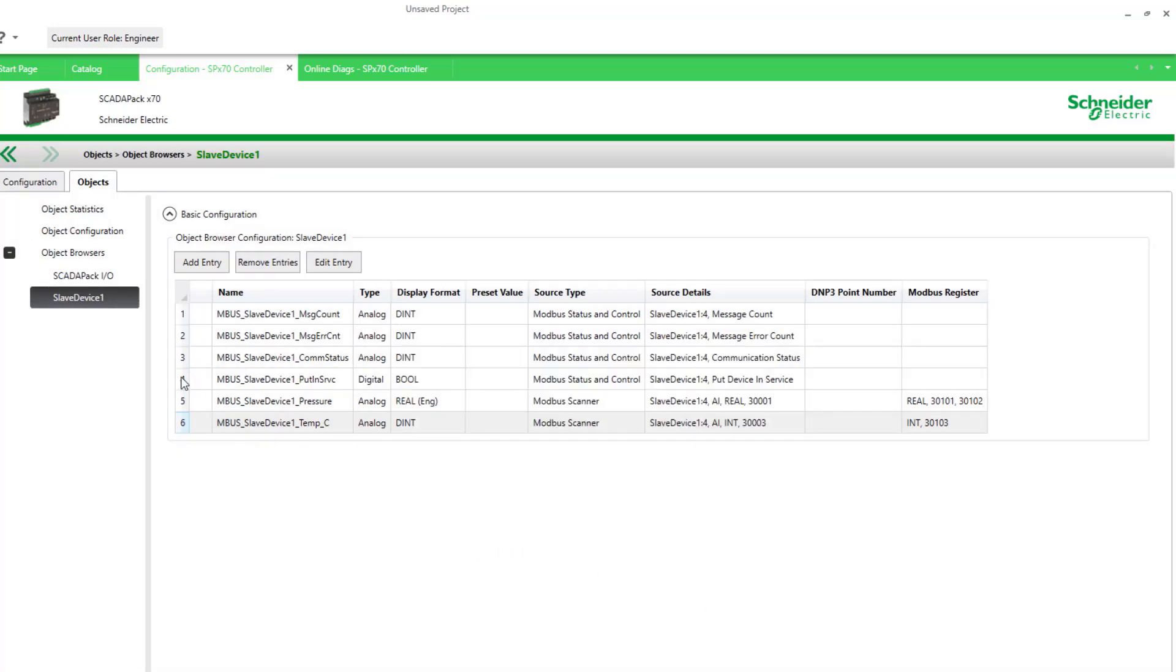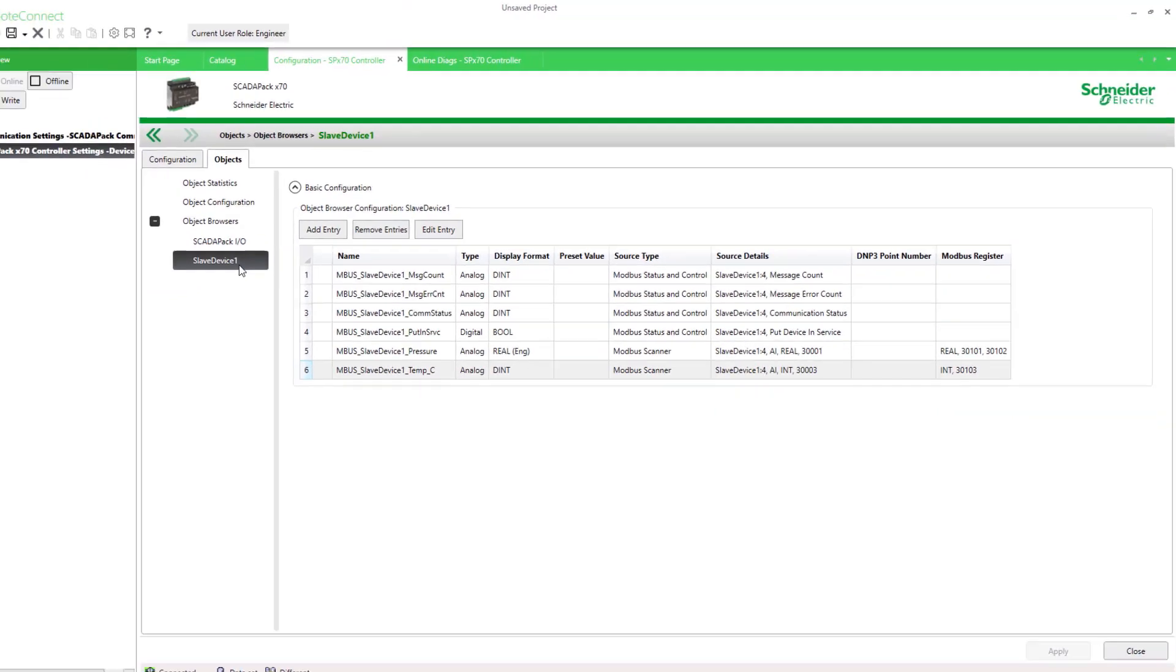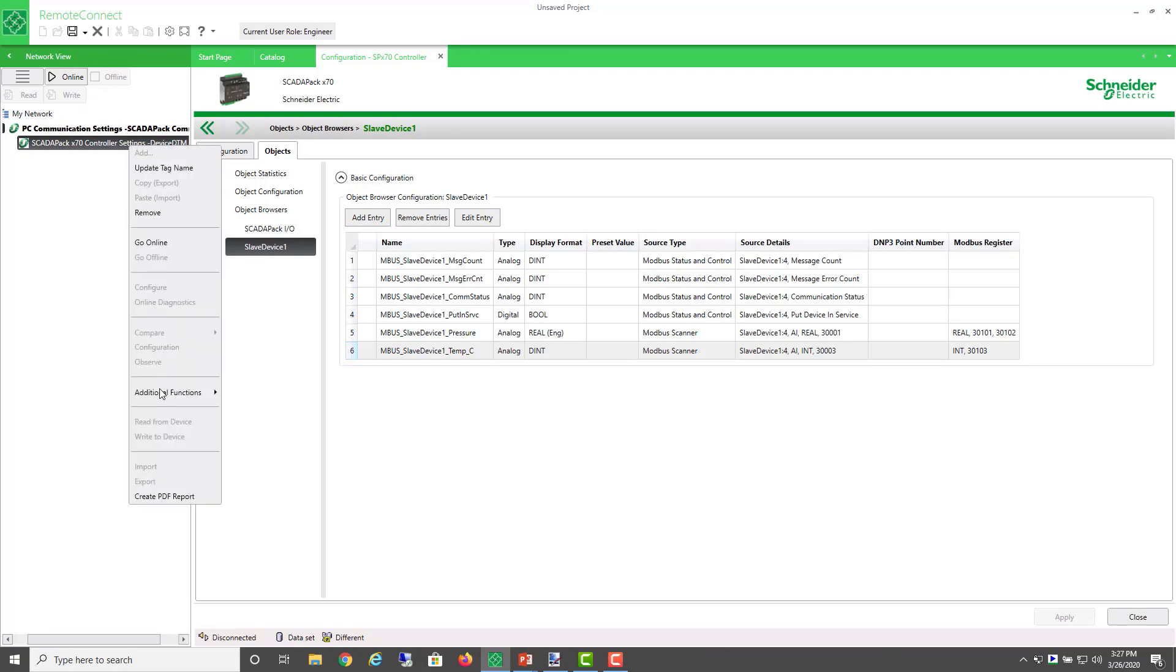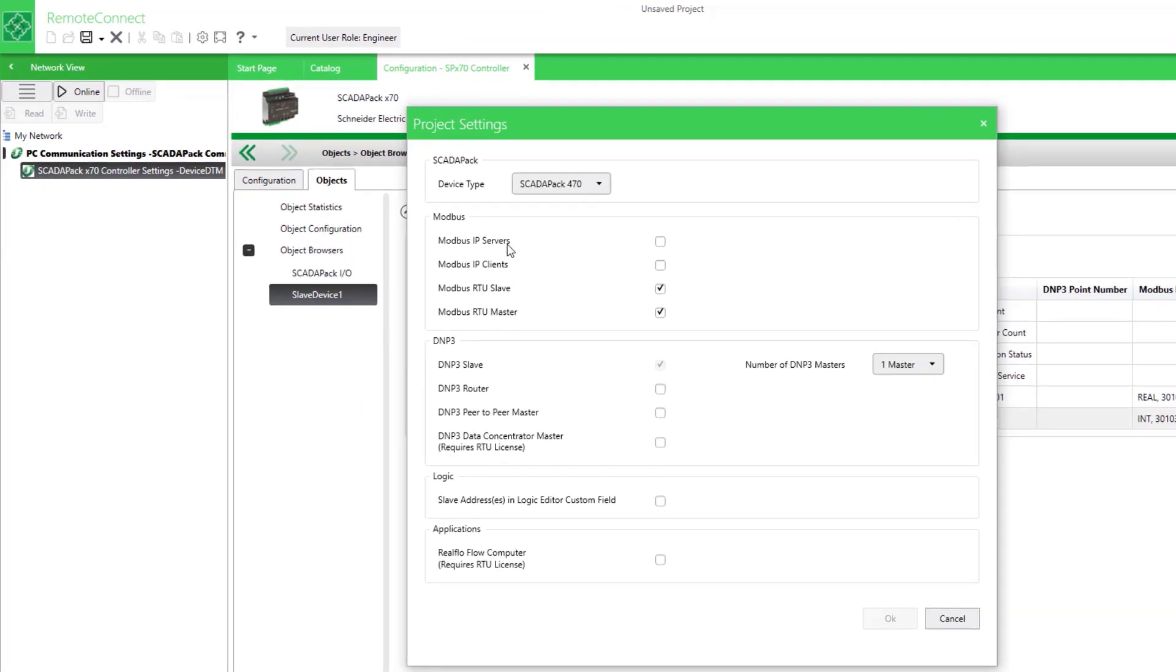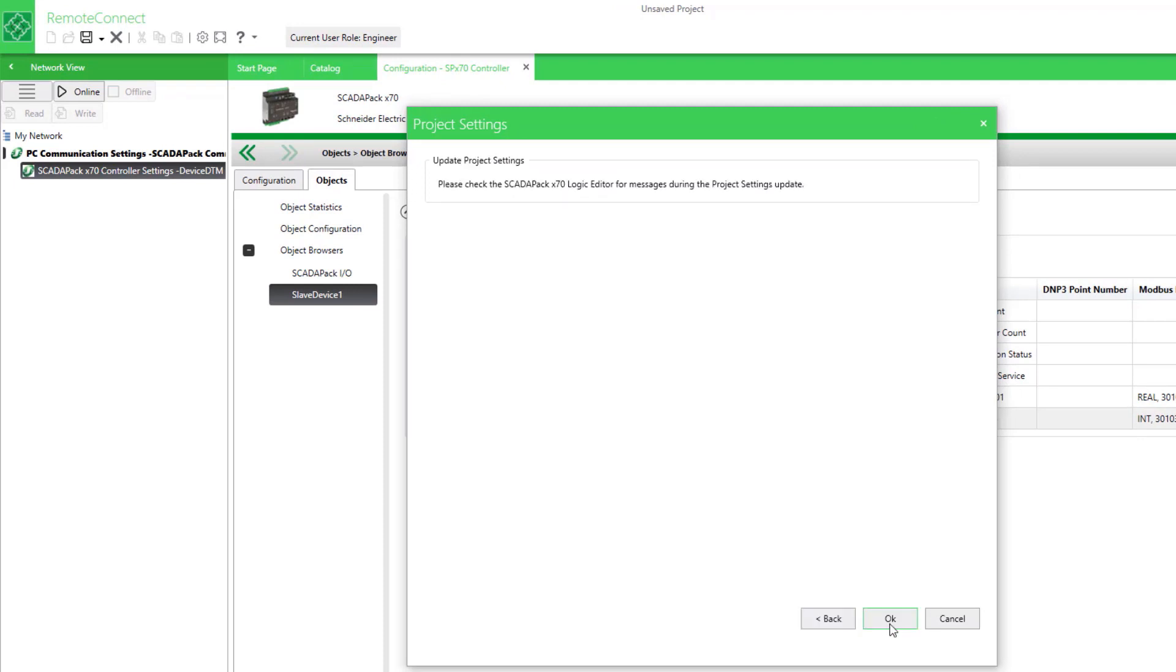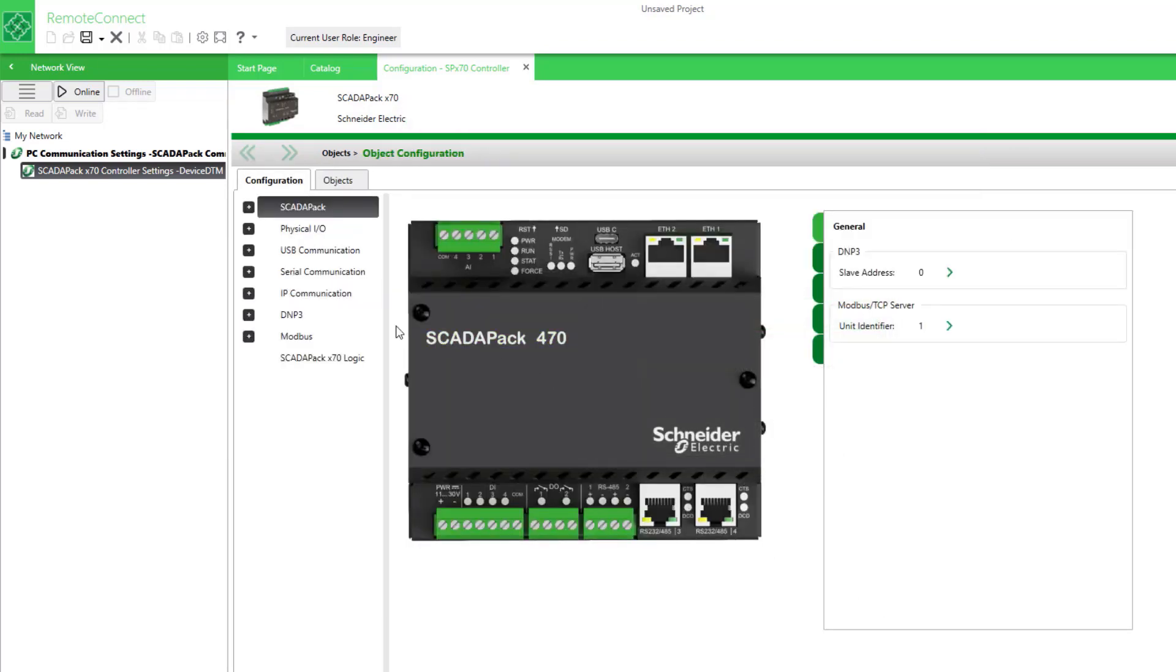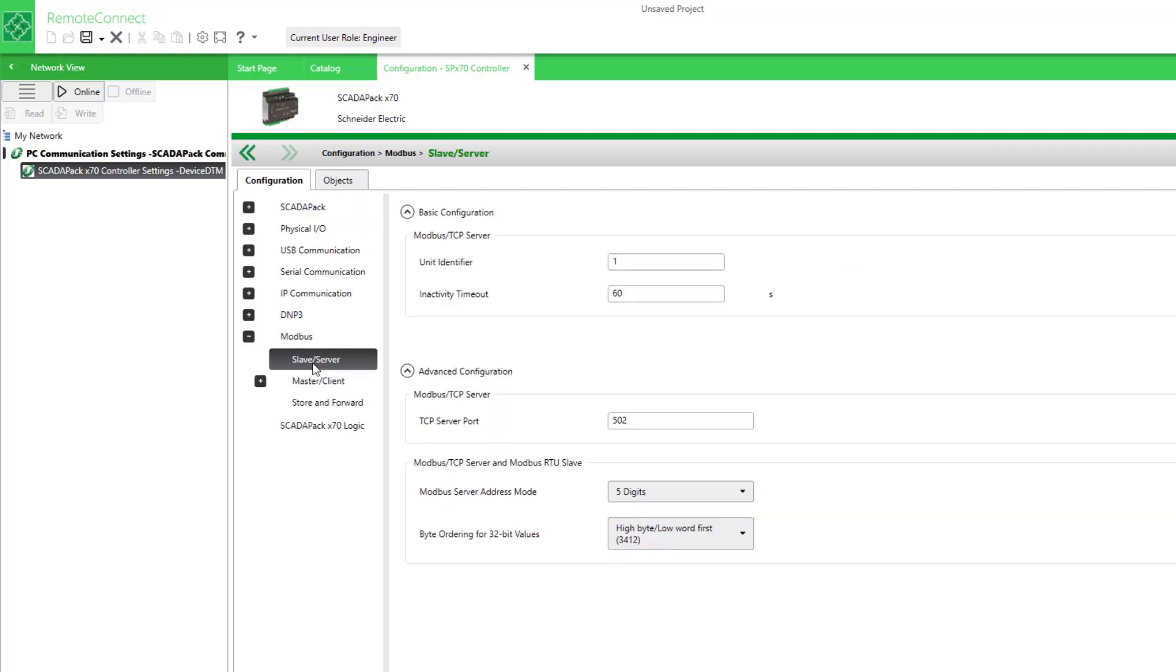Now I can write this to my controller, but there's something I need to enable first. We haven't enabled any Modbus TCP server settings. So we need to go offline, and under Project Settings, Modbus IP Server, we need to enable this one. Now, under Modbus and Server Settings, in addition to these settings we had earlier, we can now confirm we want to use the TCP port 502, and our TCP address. So this is the station address of our RTU for Modbus TCP. We'll choose the default of 1.